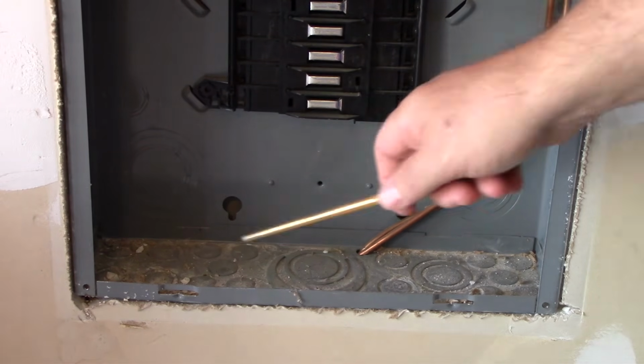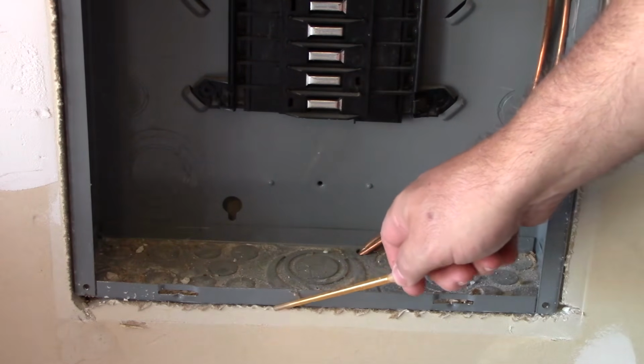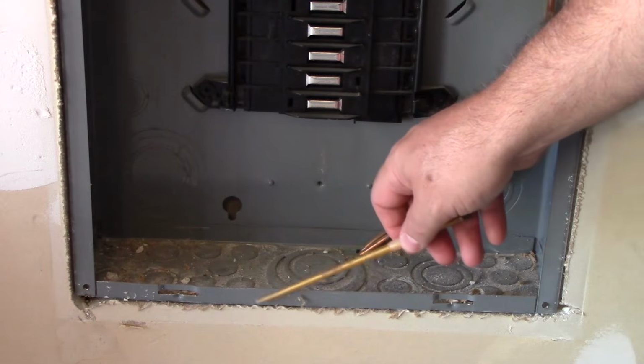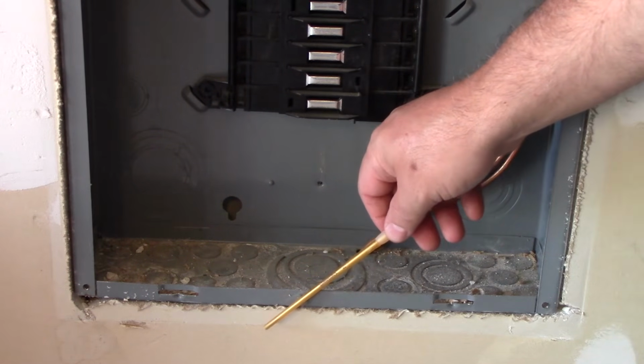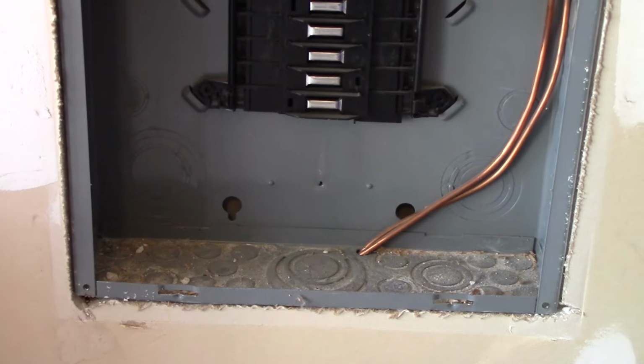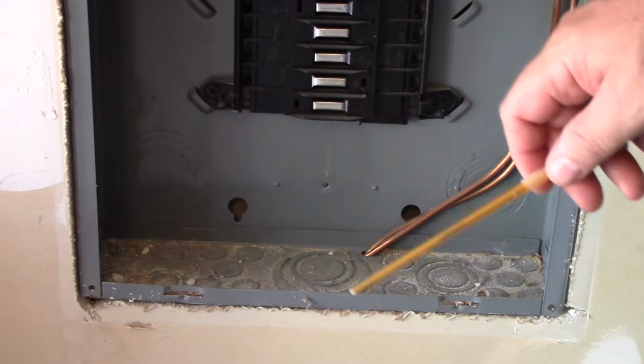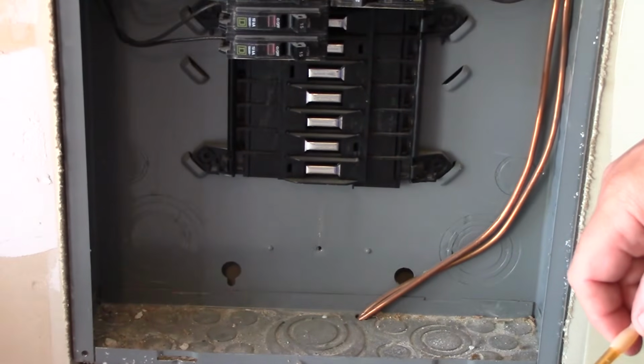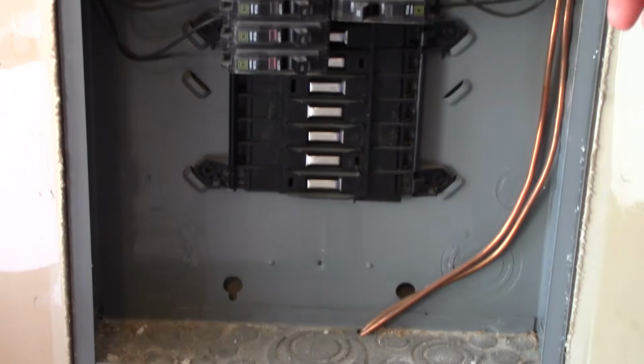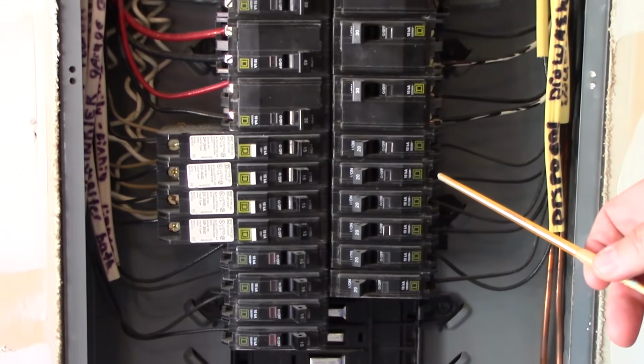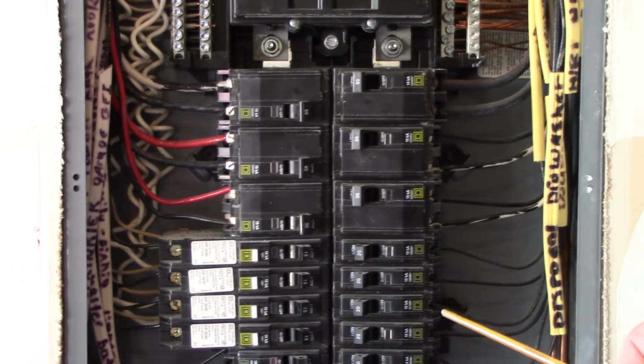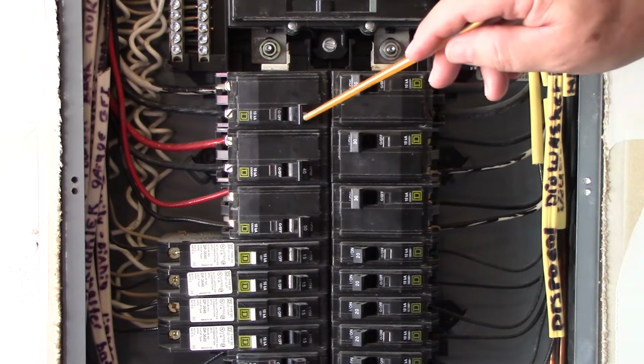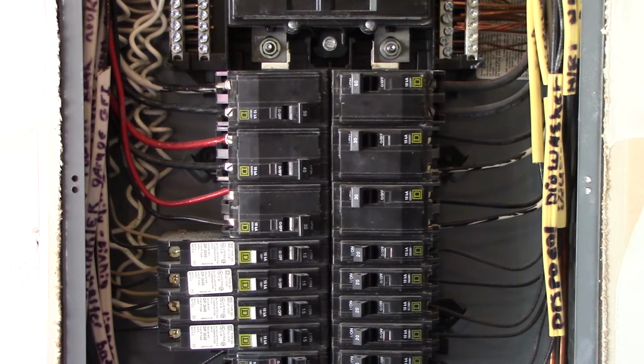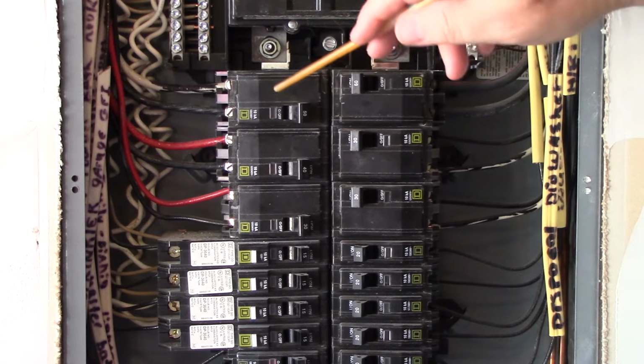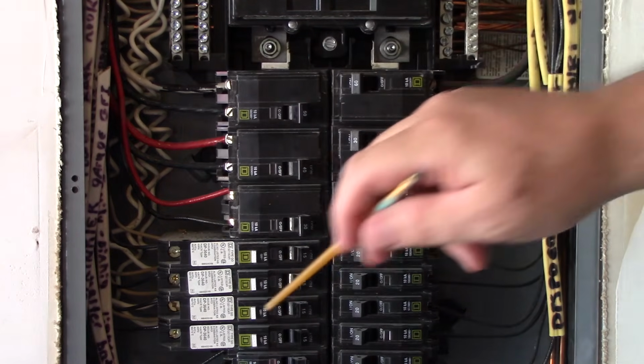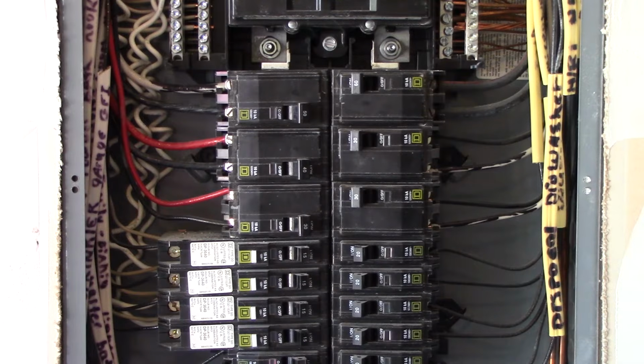We've actually looked at the gaps here to make sure that they're not more than 1/8 of an inch, that the panel's set flush. If it's combustible, it has to be flush; if it's non-combustible, it can go back 1/4 of an inch. We've talked about multi-wire branch circuits and the breaker configuration. We talked about AFCIs. We talked about the conductors a little bit. So now let's look at the sizing of these conductors. All right, so this is a 50 amp device. Okay, so this is rated for 50 amperes. And so when we look over here at these conductors, we're going to start to determine whether or not the conductors are sized correctly. All right.